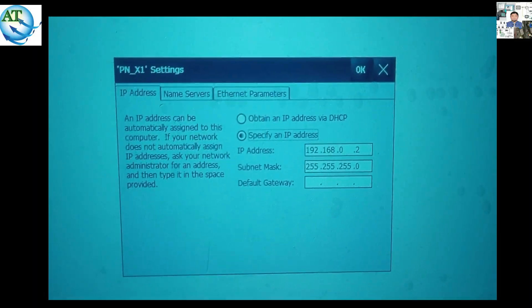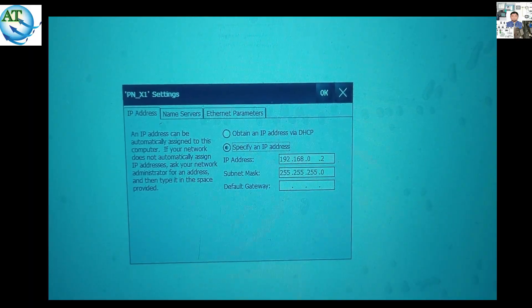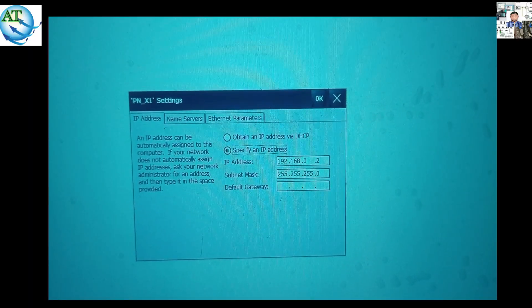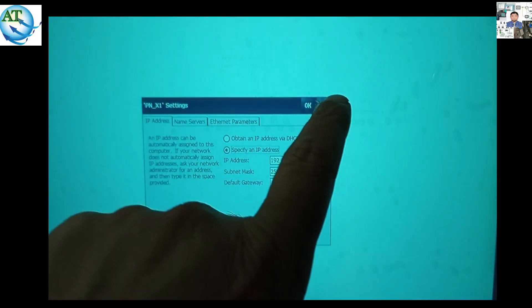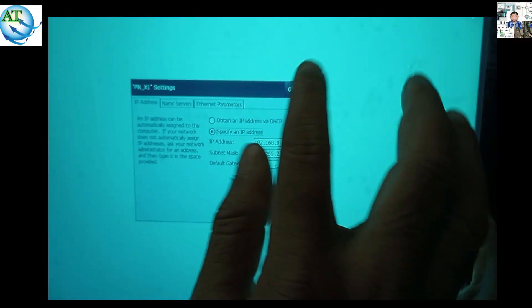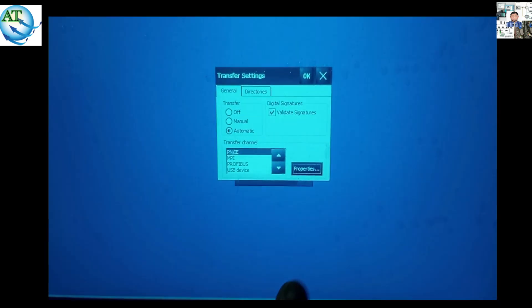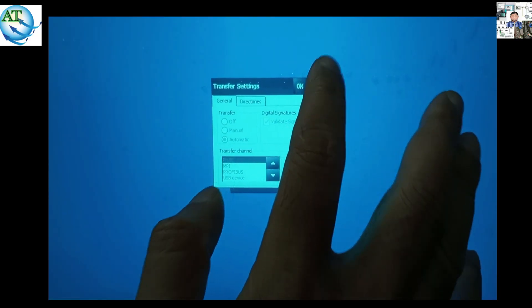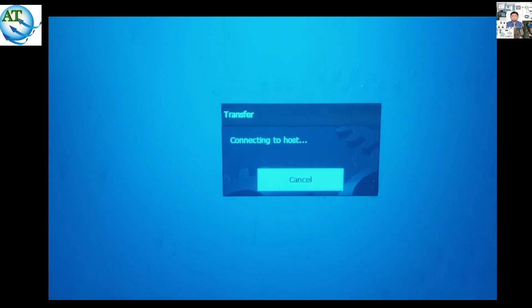It is most important that this HMI IP address series and the laptop or PC IP address must be the same. It must be in the 0 series — 192.168.0.2. The PC IP address must also be in 192.168.0.x with any other number. We record this IP address and then go to the PC side. We then press the transfer mode button on the HMI.